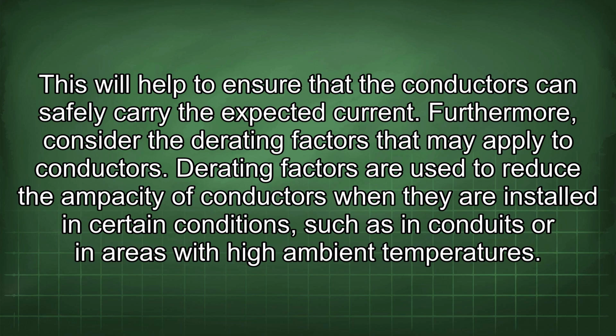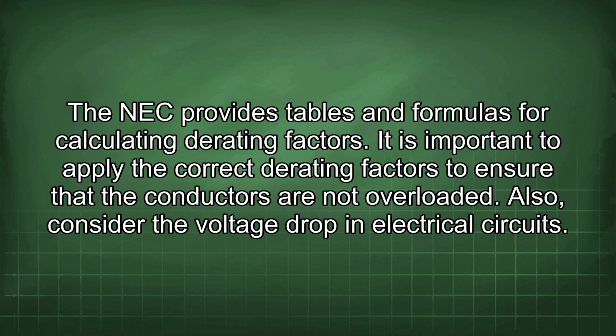Furthermore, consider the derating factors that may apply to conductors. Derating factors are used to reduce the ampacity of conductors when they are installed in certain conditions, such as in conduits or in areas with high ambient temperatures. The NEC provides tables and formulas for calculating derating factors. It is important to apply the correct derating factors to ensure that the conductors are not overloaded.